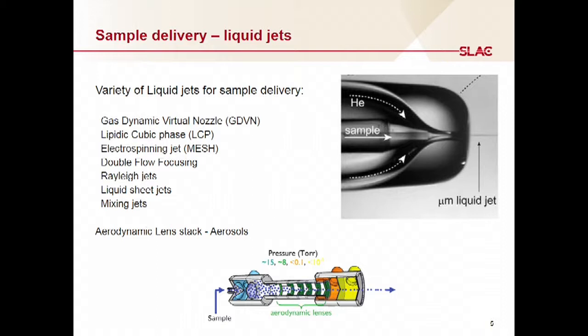There's also this aerodynamic lens stack, which is used very often for single particle imaging. What it does is it focuses aerosols. So if you want to have a solution of, say, particles or viruses, what you can do is aerosolize them. And then the aerodynamic lens stack has a series of pores which slowly focus the aerosol into a very, very small spot. For that, because of your hit rate, you want it to be very, very dense so you can have a lot of data. And if you have a very diffuse aerosol, you will never get the density that you need. So this aerodynamic lens stack is used in order to focus down your aerosol.